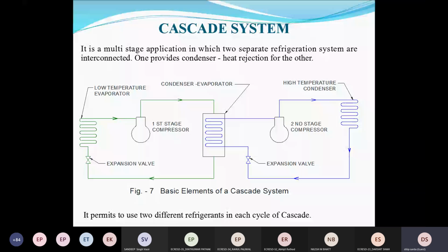Since many years, I have seen that in '91, '92 in Kandla, they import propane and butane in liquid form, store it in a cryogenic, or you can say insulated, vessel, and keep one standby refrigeration system, so it may suck the vapor from the top and again condense it and feed it back. In such a type of system, this cascade system is much more useful to us.